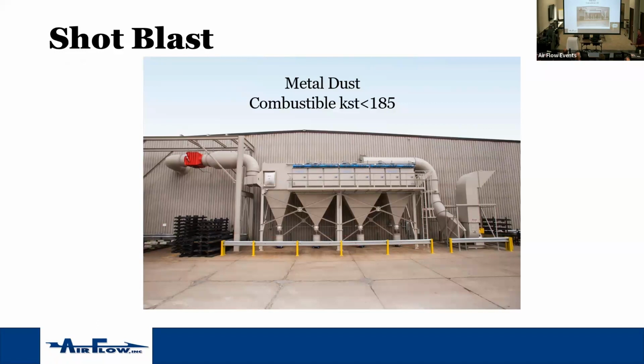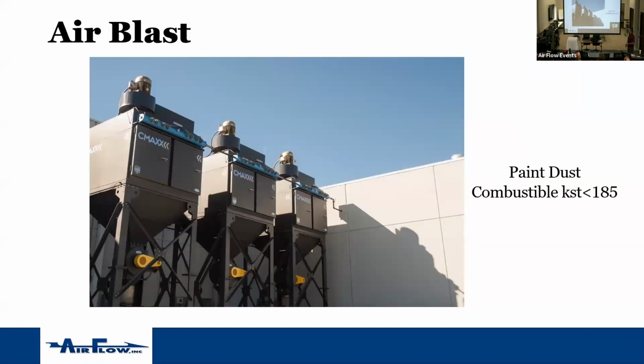Shot blast, we have our inlet protection. We have a spark trap. We have our explosion panel. We're venting it outside, so there's nothing here for an abort gate, because we're not returning the air to the space. If we were returning the air to the space, we'd have to have inline deflagration protection and an abort gate. Paint dust, same thing. You got your devices on the bottom, just kind of showing your rotary airlocks. And we're gonna hold questions for a moment.